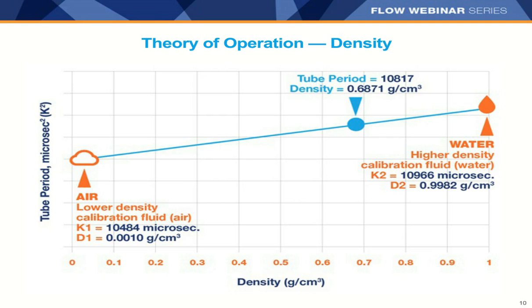Density calibration is performed at the factory on air and water. Meters filled with air result in a tube period called K1, and K2 for water. These two values are plotted against each other, making a straight line. D1 is the density of air and D2 is the density of water. Because this is a straight line and Coriolis is a linear device, we can measure anything heavier than water or lighter than air.